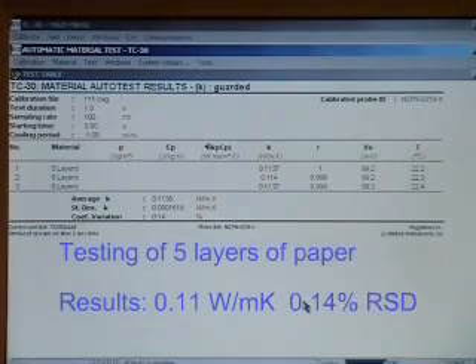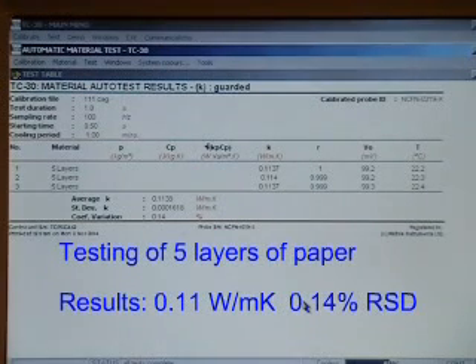Now that we've completed our calibration, I've gone ahead and placed the 5 layers of paper on the sensor and performed 3 tests using the auto-test function. Upon completion, it displays the average data along with percent relative standard deviation. Our result is 0.11 watt per meter Kelvin with a percent relative standard deviation of 0.14.